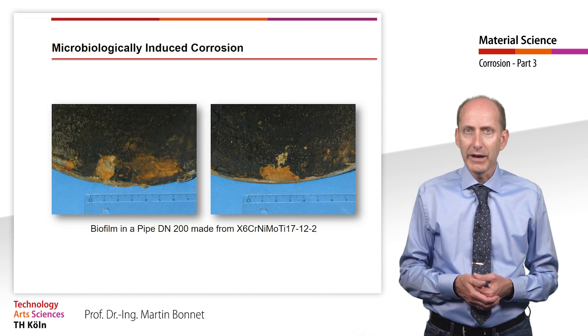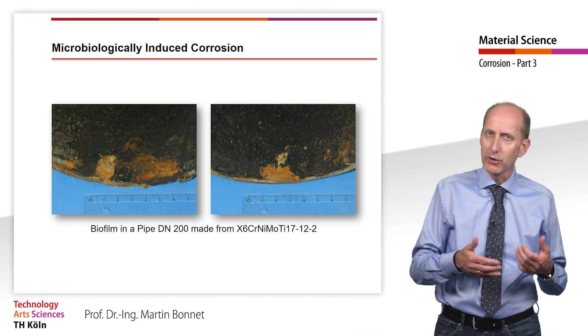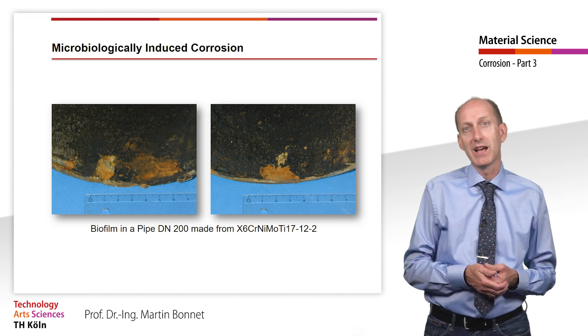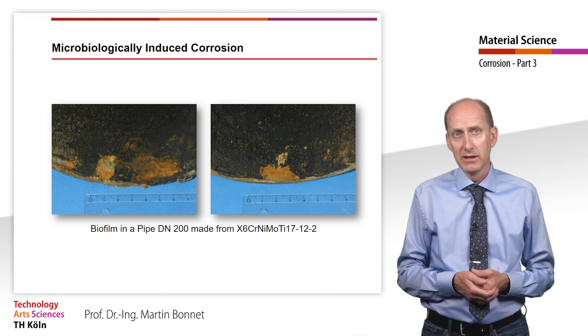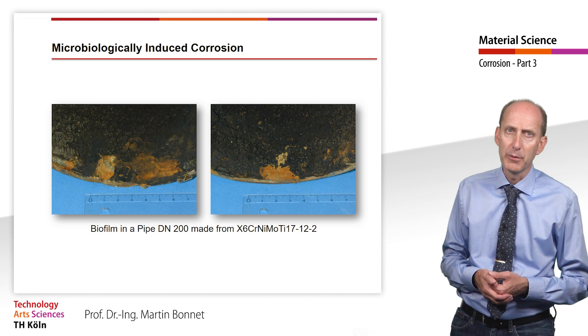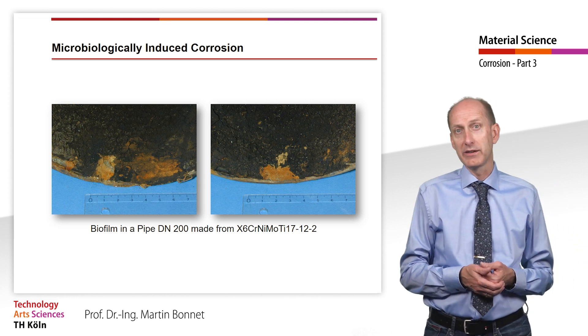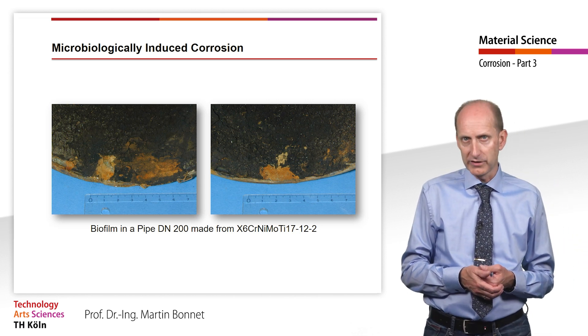Inside the pipe, the biofilm, one might even say the biocrust, became visible after cutting it open. In further investigations, the presence of manganese oxidizing bacteria was detected.